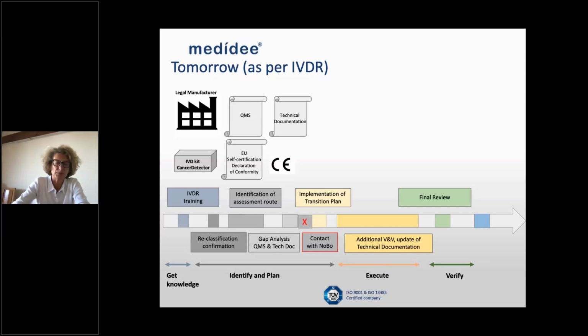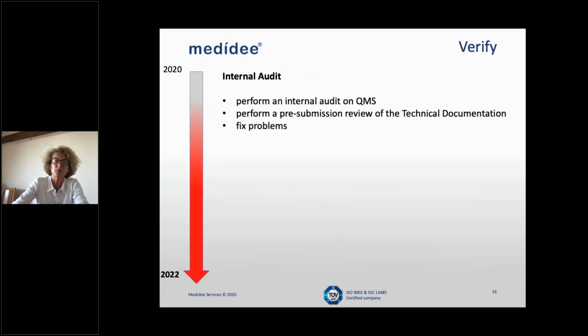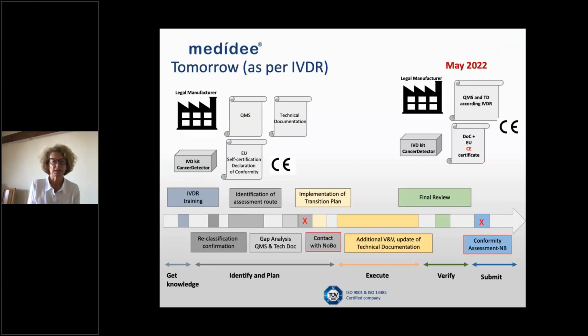The second thing to do before going into a conformity assessment by a notified body would also be to make a final review of your documentation. We strongly suggest performing an internal audit on your quality management system, and also a pre-submission review of the whole technical documentation. This will allow you to fix any problems in your quality management system or in the technical documentation up front, before going into the conformity assessment. Once you are successful, you may go on to the conformity assessment with a notified body.